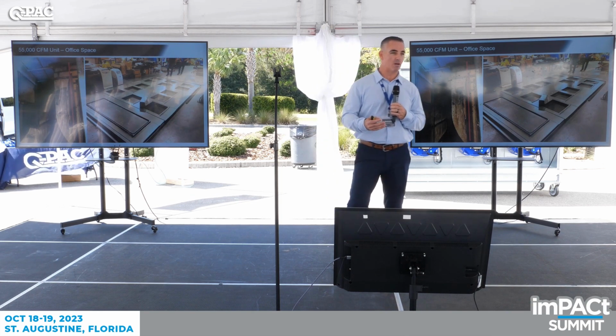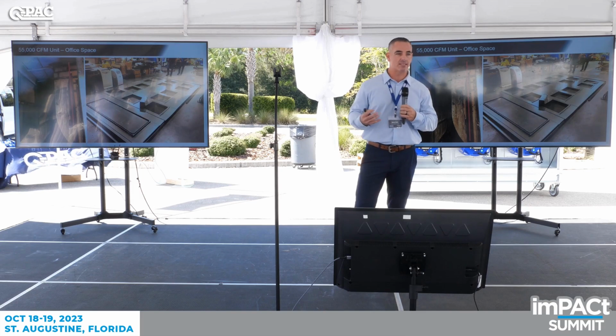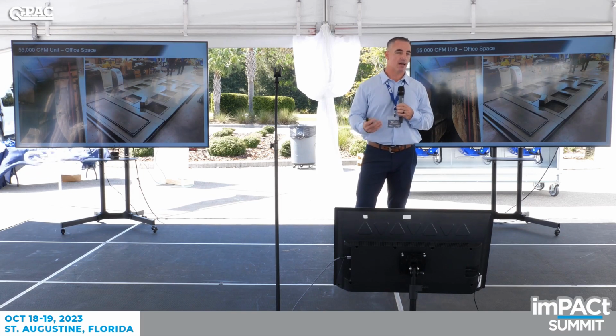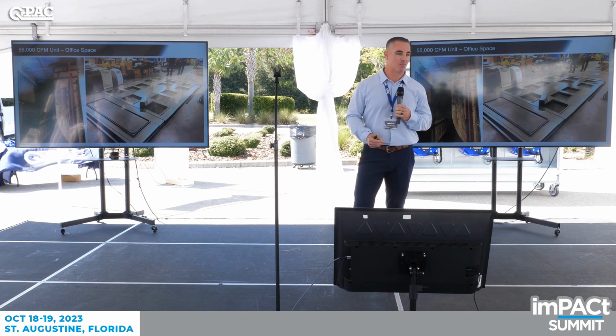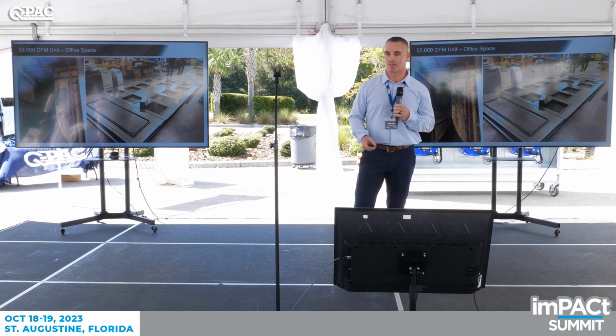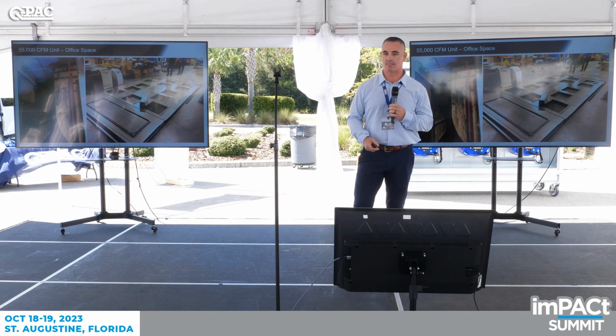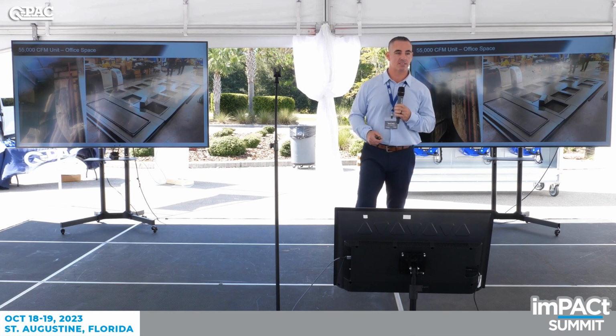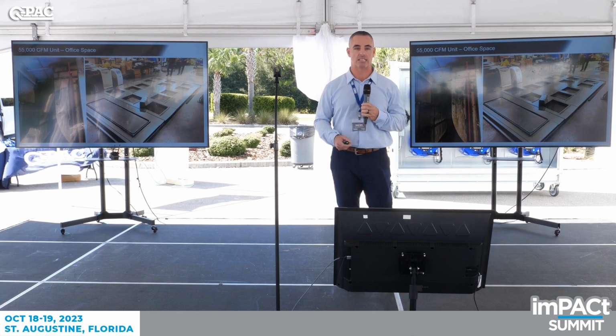If they have to put angle or sheet metal or patch any holes, you need to seal that, and it's advantageous to tell the customer this is what's going to happen and you're going to be positive. I'm not too worried about the static. A lot of these units are robust and can handle it. If I was doing 9.5 inches of static, I'd really need to look at the unit.